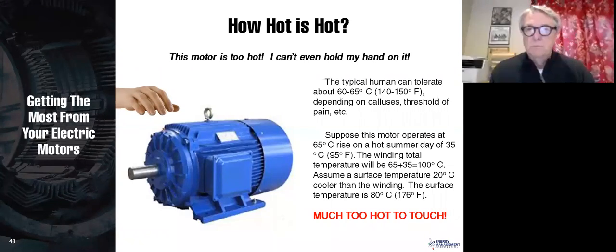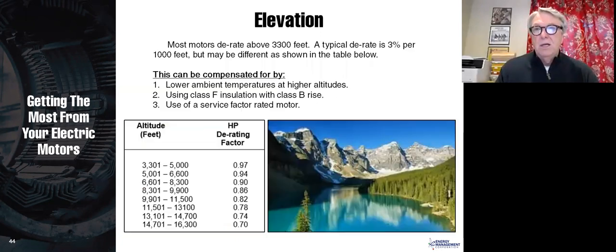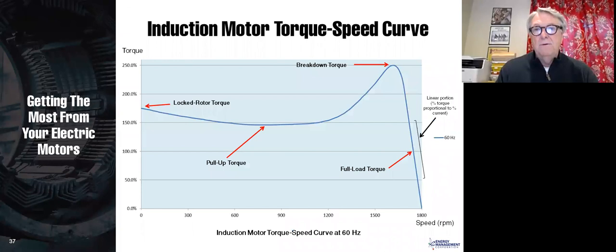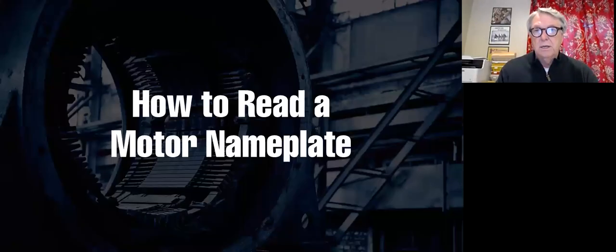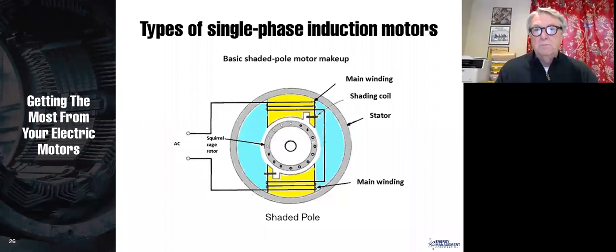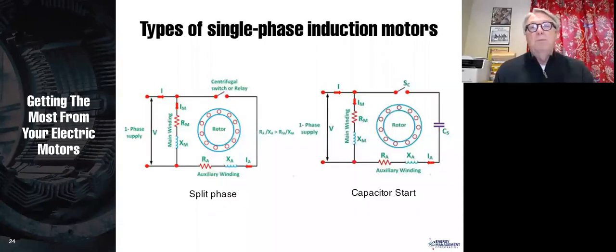All right, next, what does split phase mean? So split phase, we will go back here. It means that you have, and I apologize, I'll find it here in a second. Right there is a split phase motor. A split phase motor is one of the 5 main types of single phase motors. You have a main winding, then you have also a second winding. And that second winding is put in a different slot on the motor, so the flux on that winding is at a different phase angle, and therefore it creates a rotating flux on the stator.